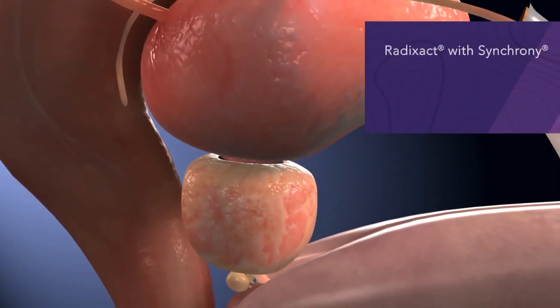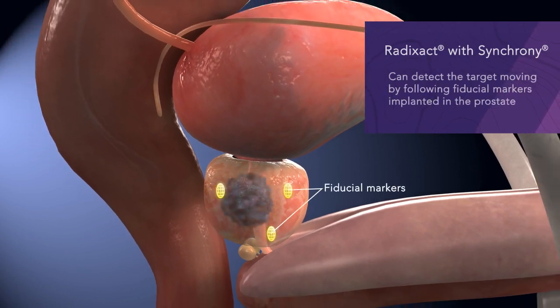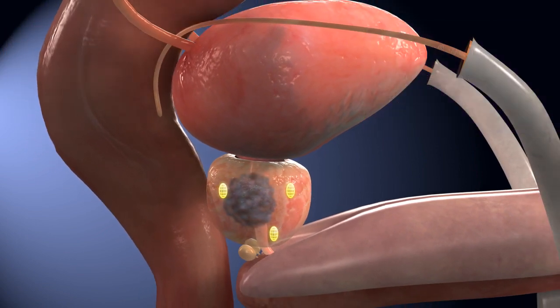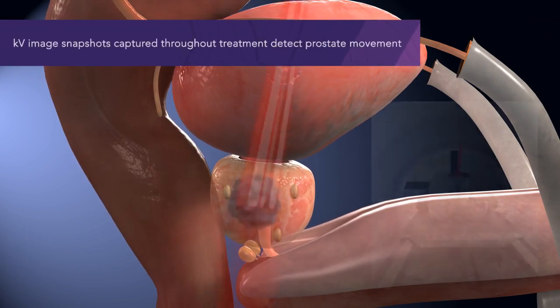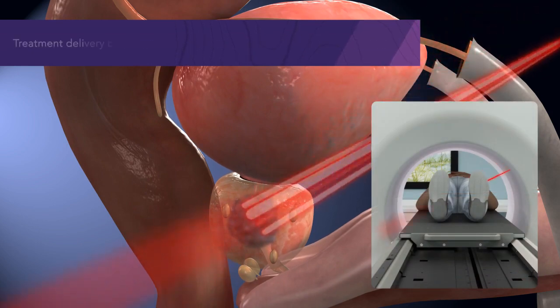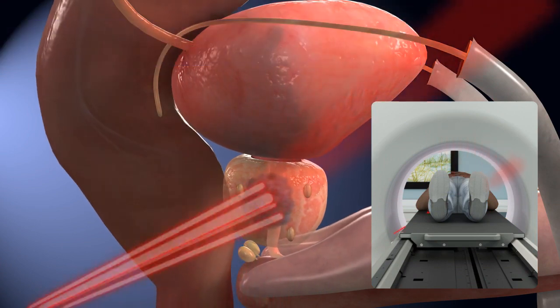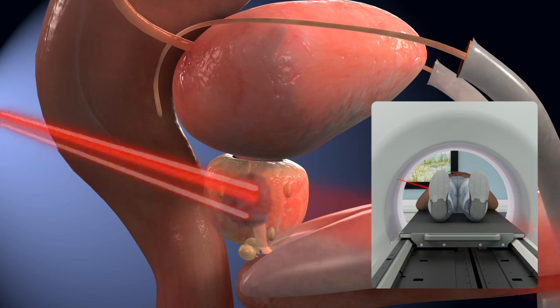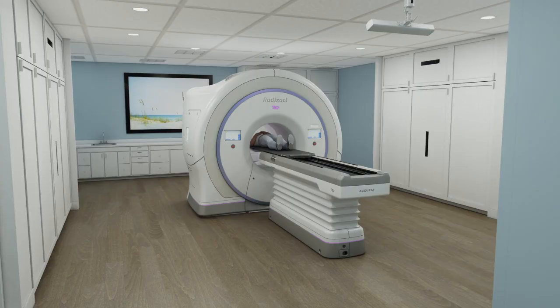The Radixact system with Synchrony can detect the prostate's position during treatment using one or more implanted fiducial markers. KV image snapshots are captured during treatment to verify the prostate's location. When the prostate moves, the Radixact system detects this movement and synchronizes the treatment delivery beam to the new position in real time, allowing treatment to be continuously delivered with submillimeter accuracy, even as the prostate moves unpredictably.